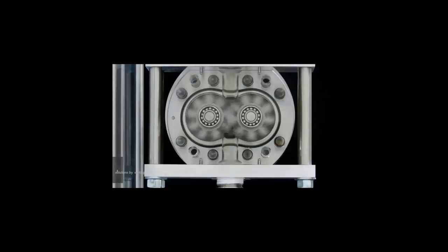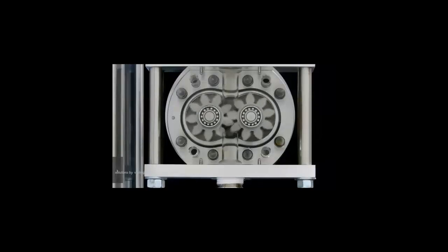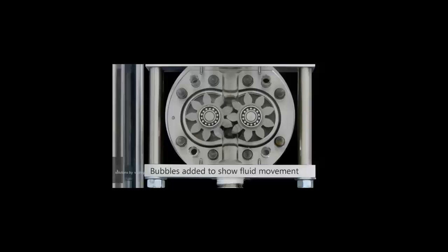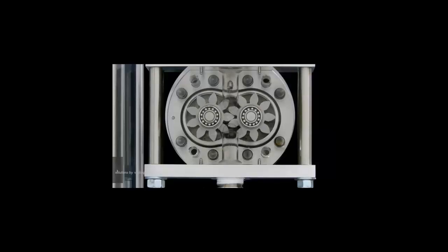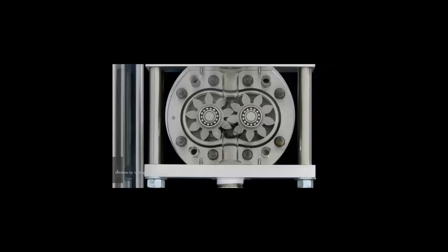Shown here is a cutaway of a positive displacement meter. Notice the gears continually spinning as fluid passes through the meter. A magnetic pickup is located on top of the meter that counts the revolutions of these gears. These revolutions and counts equate to flow volume. This is what is stored by the data logger.